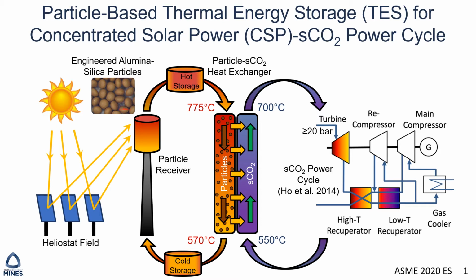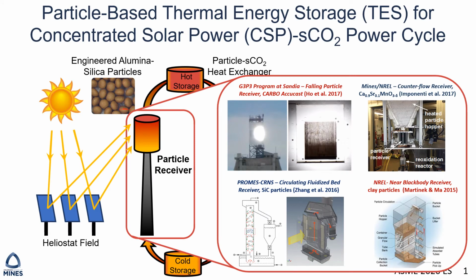The heated particles feed the hot side of a particle SCO2 heat exchanger, where the solar heat captured in the particles is transferred to the SCO2 to drive a Brayton power cycle like that shown on the right. The cooled particles are then collected and recycled back to the receiver. Of the subsystems necessary for implementing particle-based thermal energy storage for CSP, the particle receiver has received the most attention, with some prominent examples shown to the right.